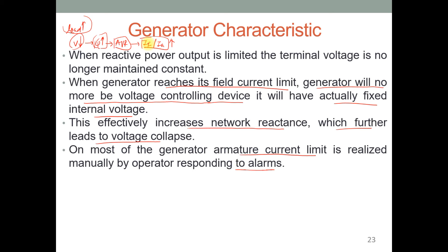Clear? Most of the generator armature current limit is realized manually by the operators responding to alarms. If the alarms indicate that IF or IA is at its maximum limit, then the operator comes into the picture and maintains the armature current limit. Clear?